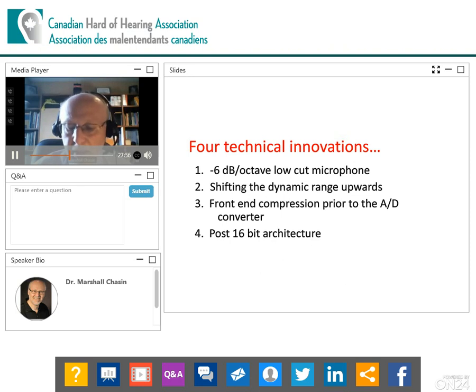Another strategy that a lot of manufacturers use now is, while the signal is still in analog form and comes through the microphone, they have a compressor which reduces the sound, applies it to the digitization process, the analog to digital converter, and then once in, it is digitally reestablished. And again, it's like ducking under the bridge. And most recently, there are what we call post-16-bit architecture hearing aids. Up to even a year ago, all hearing aids were 16-bit. And all that meant is that they couldn't really handle inputs louder than about 95 decibels.